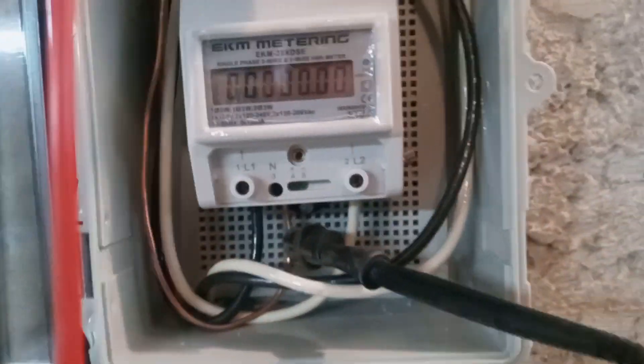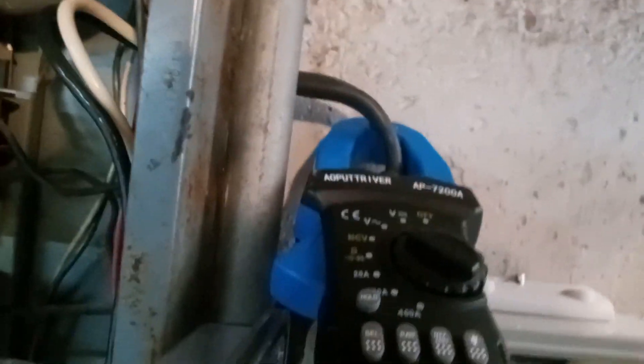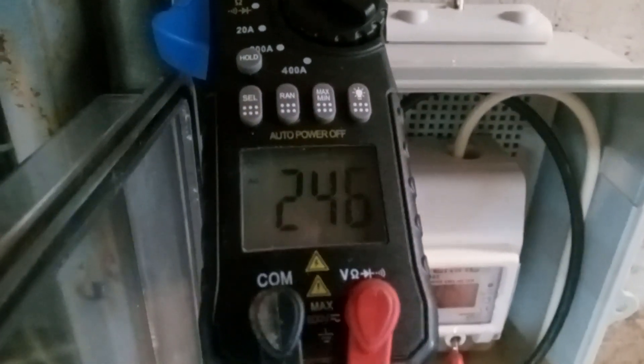What's going to happen when we power this thing up? I don't know — let's see. That first-floor light seems to be on this, but — okay, I got a digital readout. Zero, zero, zero, zero, zero. Let's check our voltage on this thing here. Now we need to check these two screws that tapped into the wire. We're going to check L1. On L1 we got 120 volts. On L2 we got 123 volts. I do have a digital display there — it's not backlit, but it's all reading zeros. So we know we have a good control. Let me get a reading between the two, L1 and L2. We should read 240. All right, so we're in business. We can put that cover on. We know our taps are good because we've got voltage on both of those.